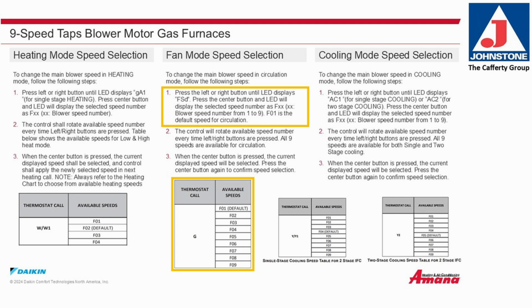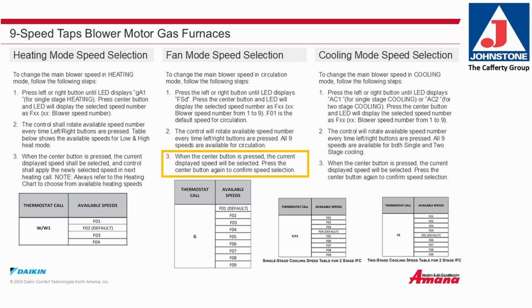F01 is the default speed for circulation. The control will rotate available speed number every time the left or right buttons are pressed. All 9 speeds are available in circulation mode. When the center button is pressed, the current speed that is displayed will be selected. Press the center button again to confirm that speed selection.